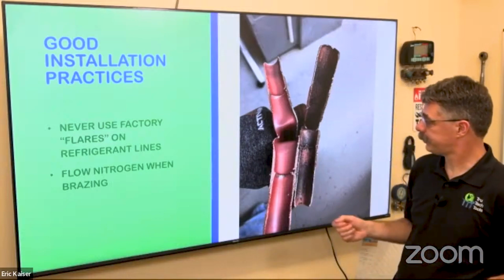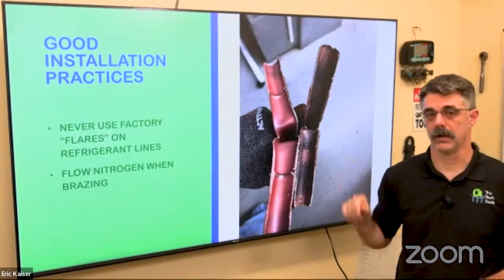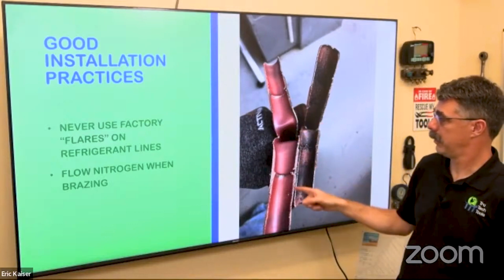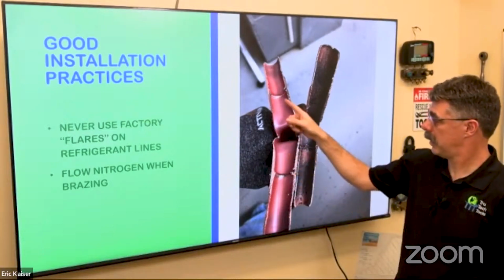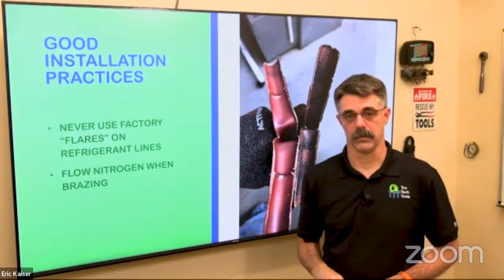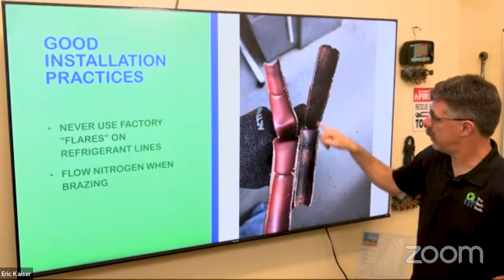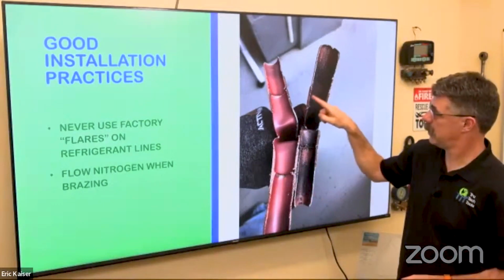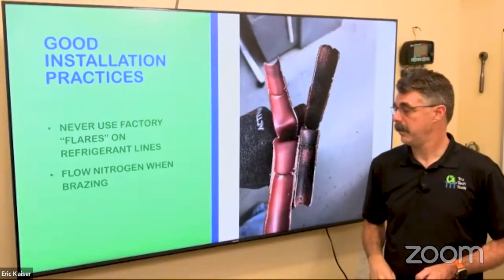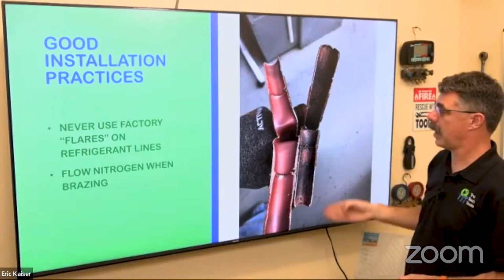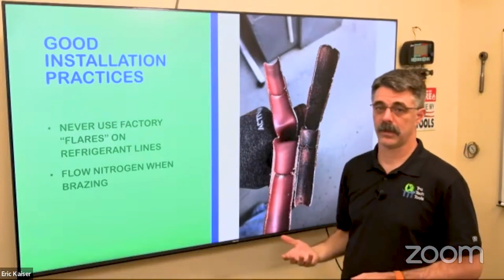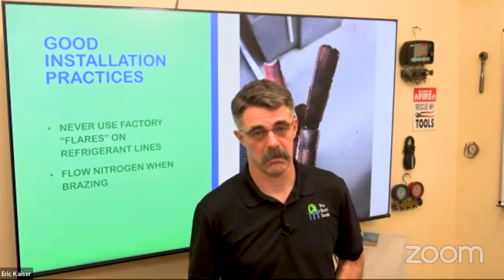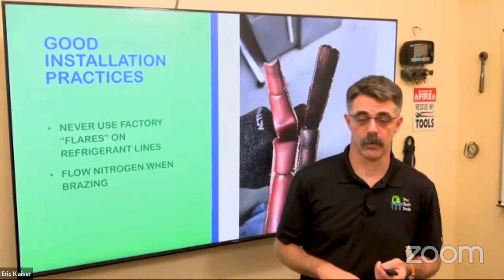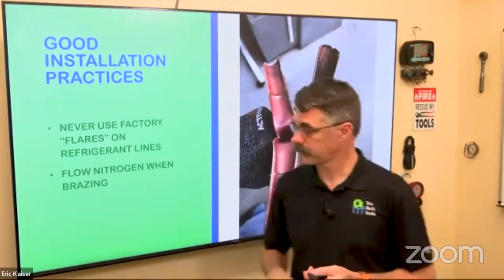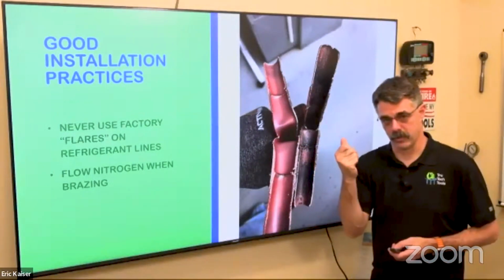Okay. And if you notice over here, there's two pieces of copper. This one here on the left, I flowed nitrogen through. The one on the right, I did not flow nitrogen through when I brazed the joint in that copper line. This is literally the difference. All of this black oxidization in here will flake off inside a refrigerant system and end up somewhere. Maybe it ends up in the filter dryer, best case scenario. But it's got to flow through other components. It's got to flow through the compressor. If you ever get a chance to feel this, it's gritty and it's abrasive.